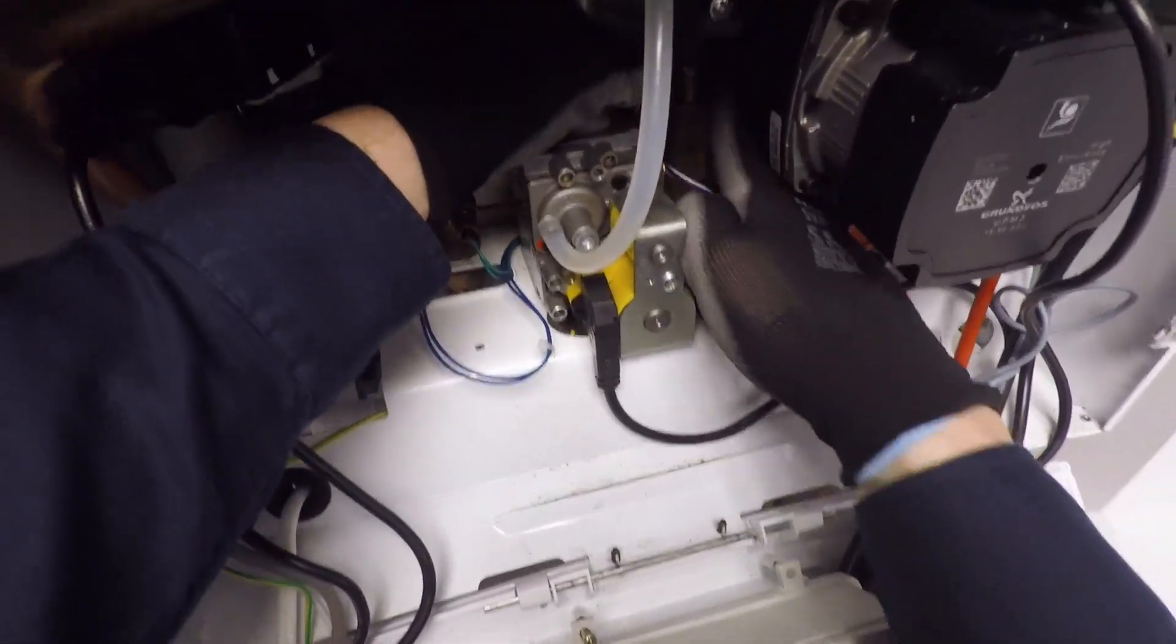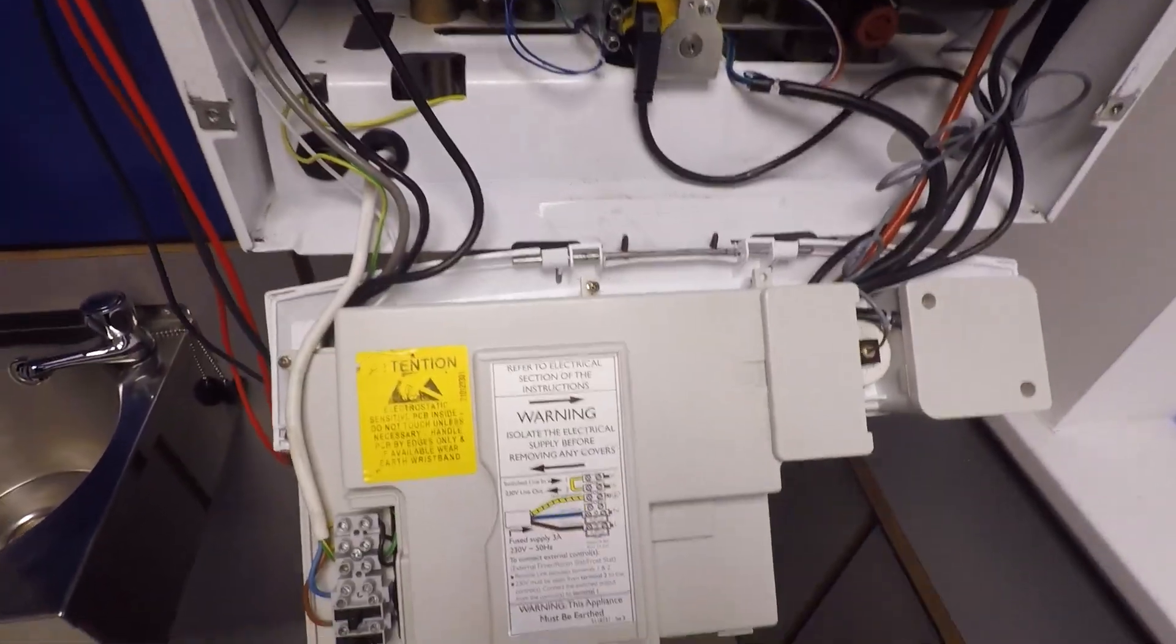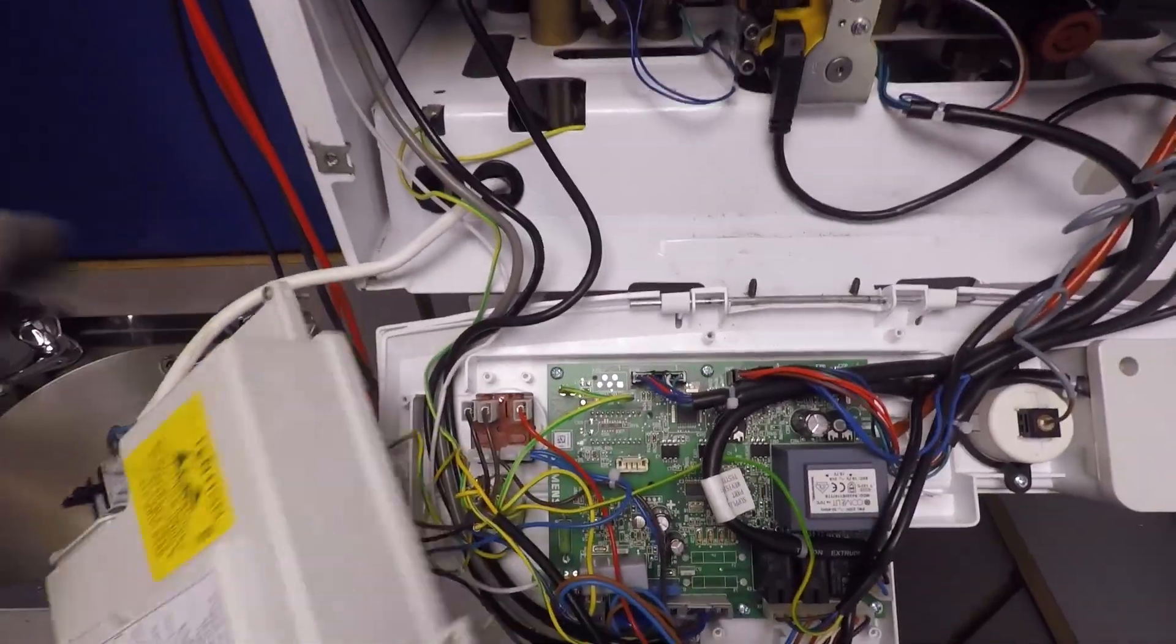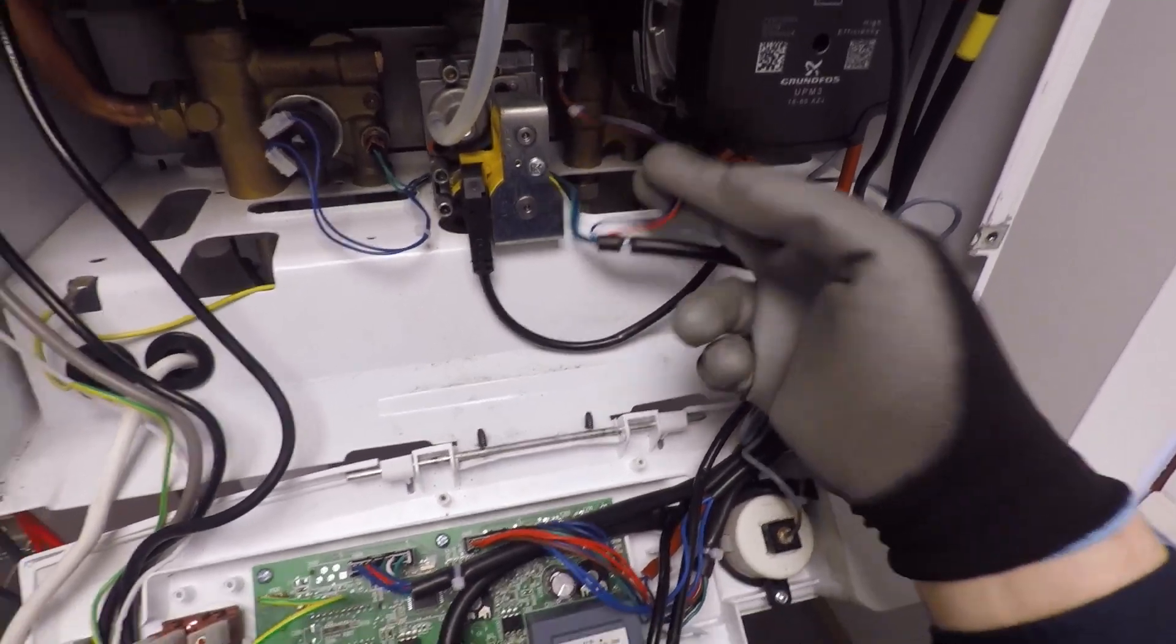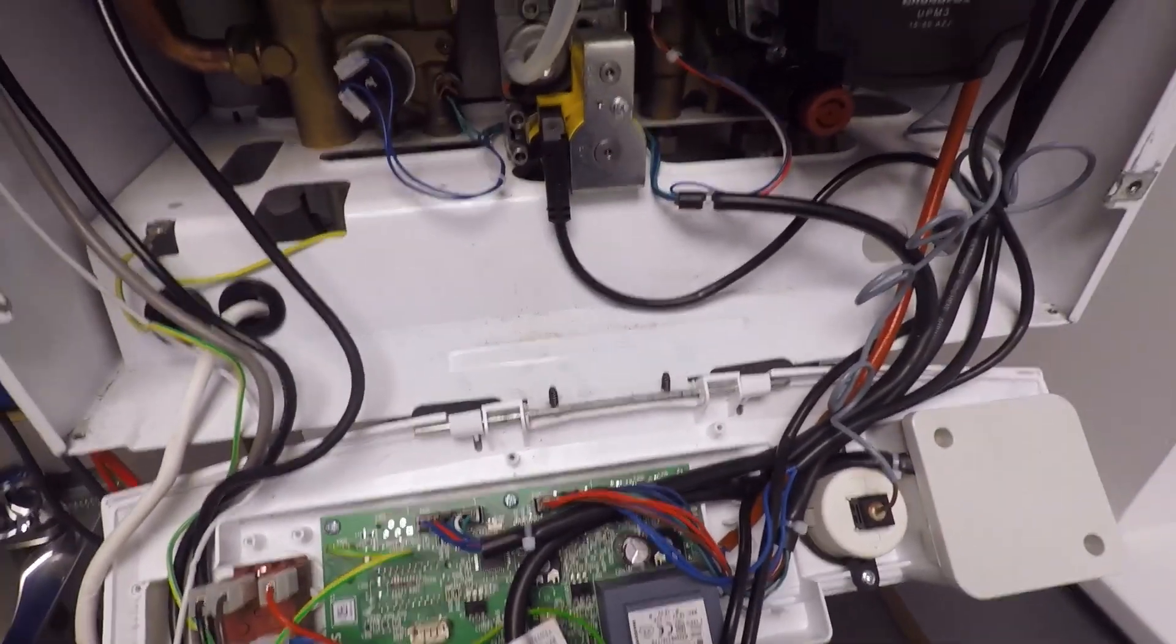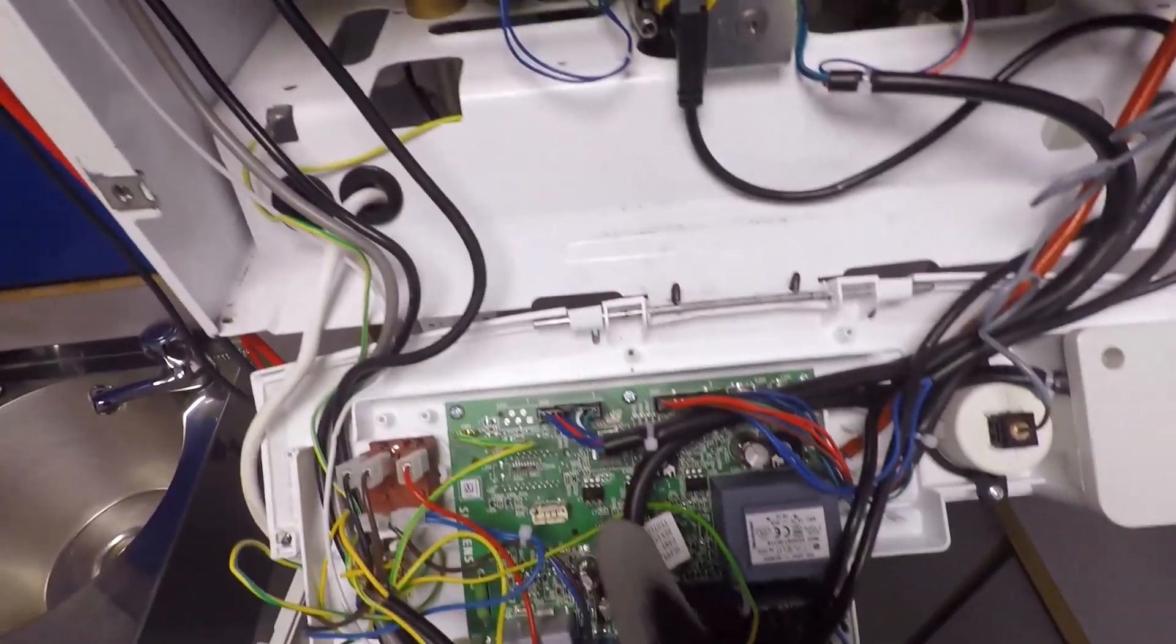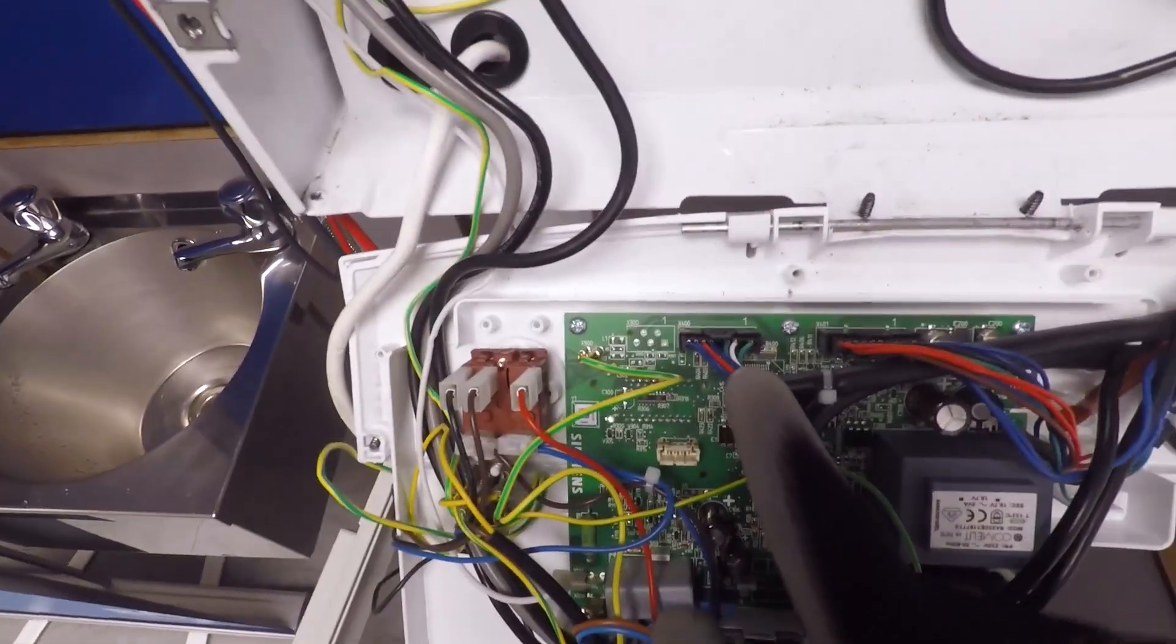But going back to your original question, can you check the voltage on them? Yes, you can. The way you do it, you need to access the circuit board, so you've got to be quite careful because obviously everything's all turned on. We already know the wires are red, white and blue. And looking at the thickness of them as well, you're looking at a low voltage there, so around about 7 volts DC. So you follow it all the way back and what you will find is the Hall Effect sensor lives on X400.